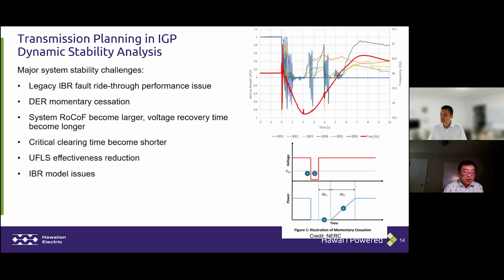Every single IBR in this event went to momentary cessation or unexpected behavior. And we didn't see this in our study because we later found out that all those models had issues. I think several panelists in today's meeting mentioned that. And the DER momentary cessation can be represented in the lower figures. Basically, when the voltage at a DER terminal, or their applicable voltage, drops below a certain threshold, the DER stops generating active power. And after voltage recovers above the threshold, with a certain delay, the DER starts recovering active power generation with a ramp rate limit.